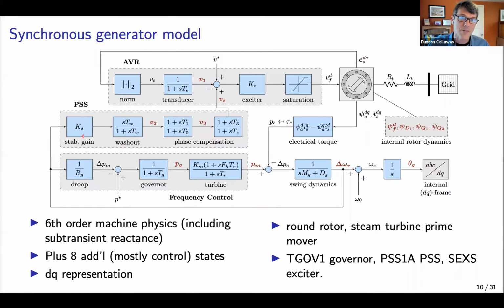And then finally, we've got this power system stabilizer block. As we started layering more and more synchronous generators together in the last century, what folks found was that there were some large instabilities that could arise, where one synchronous generator would essentially swing against another one, meaning that they would start to have modes of oscillation that get bigger and bigger and bigger. A power system stabilizer's purpose is to prevent those modes of oscillation from emerging. So this is like a wrapper control loop that adjusts the torque that that generator provides to the grid in order to ensure that, at least for some modes of instability, that synchronous generator is stable.